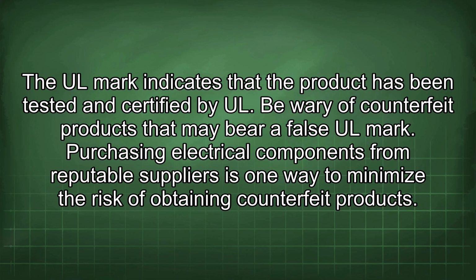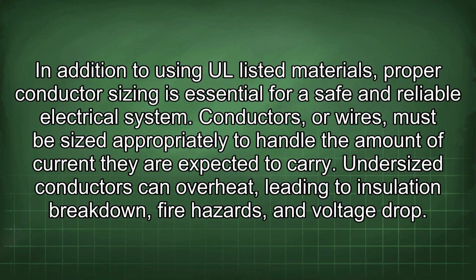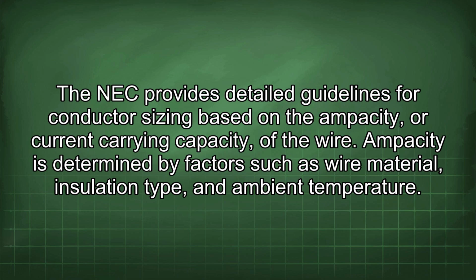Purchasing electrical components from reputable suppliers is one way to minimize the risk of obtaining counterfeit products. In addition to using UL-listed materials, proper conductor sizing is essential for a safe and reliable electrical system. Conductors, or wires, must be sized appropriately to handle the amount of current they are expected to carry. Undersized conductors can overheat, leading to insulation breakdown, fire hazards, and voltage drop. The NEC provides detailed guidelines for conductor sizing based on the ampacity, or current carrying capacity, of the wire. Ampacity is determined by factors such as wire material, insulation type, and ambient temperature.